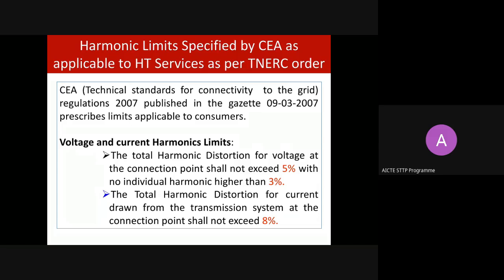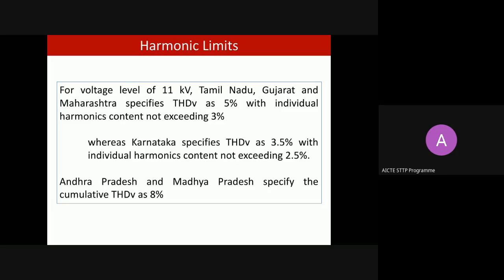Okay, now we are coming to the harmonic limits for Tamil Nadu state. We are giving more focus to HT consumers. For voltage levels of 11 kV and above, Maharashtra, Tamil Nadu and Gujarat all fix 5% as THD, as we discussed already, and 3% for individual harmonics. Whereas Karnataka is further stringent: they reduced THD to 3.5%, with individual harmonic current content not exceeding 2.5%. If you think about Andhra Pradesh and Madhya Pradesh, they have THD of 8%.